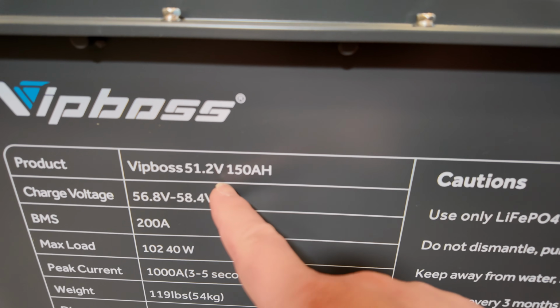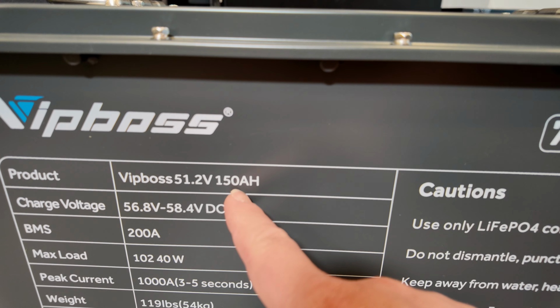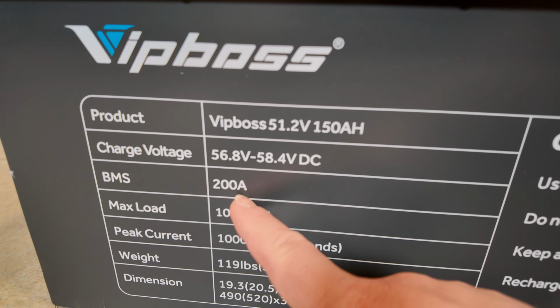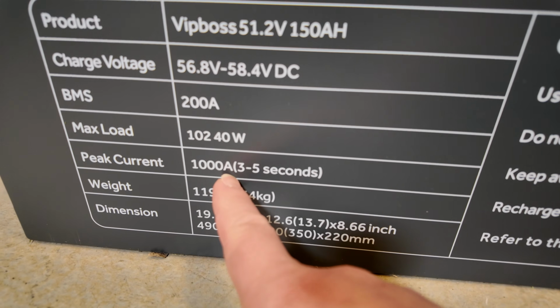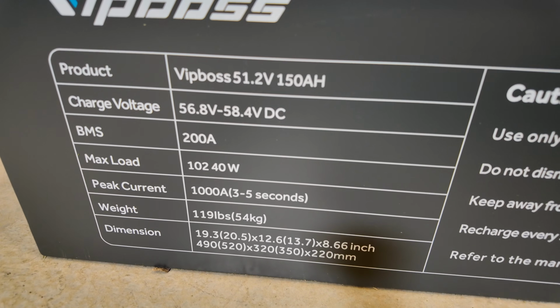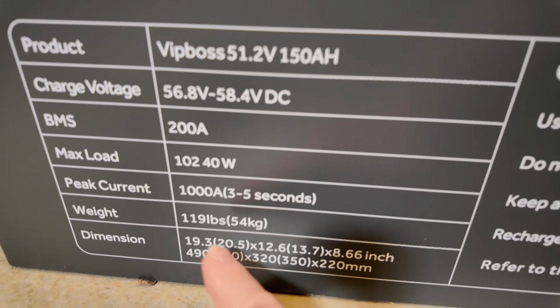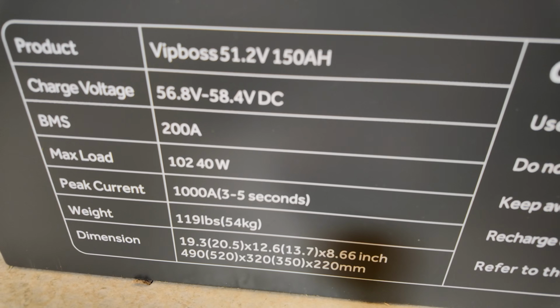So it's a 51.2 volt, 150 amp hour battery with a 200 amp BMS. Surge rating 1000 amps for 3 to 5 seconds. That is a lot of current. And yes, be aware it is very heavy, 119 pounds.